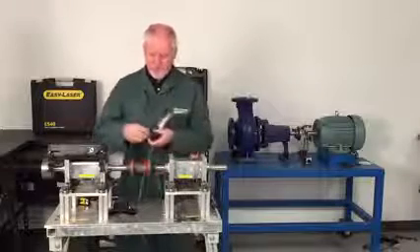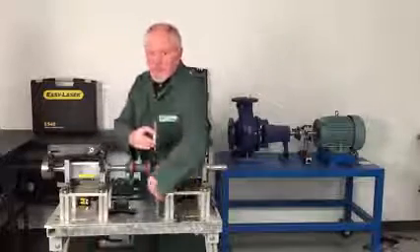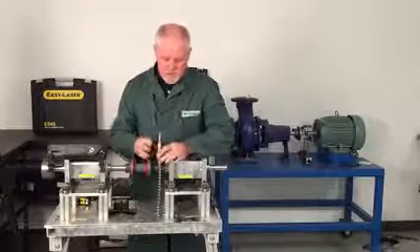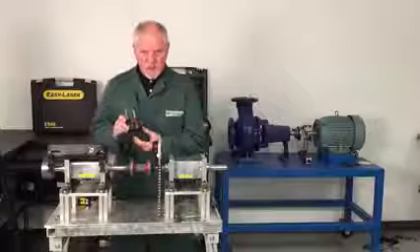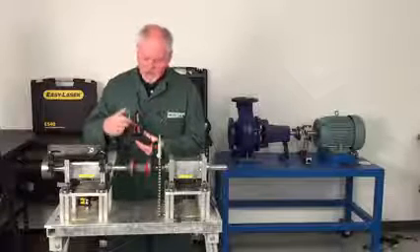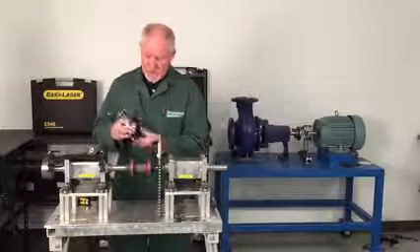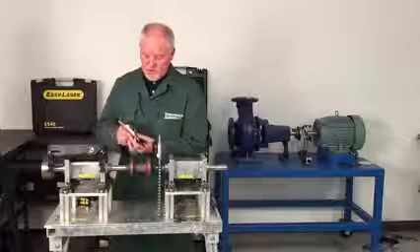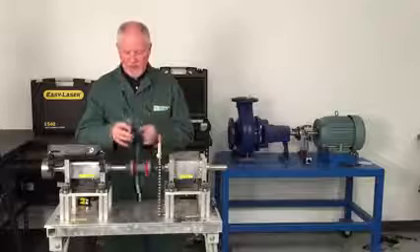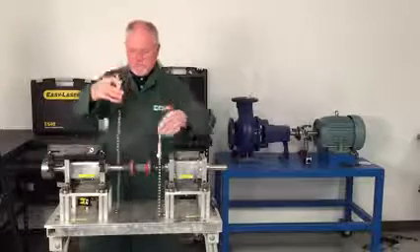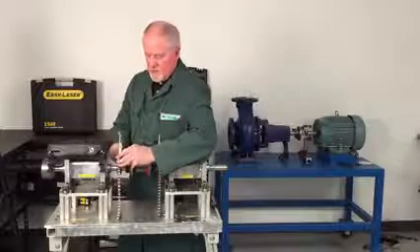And to mount it, all I do is hang the chain from the bracket, pass it under the shaft, and put it on the pin, tighten it up. Now this is exactly the same unit. When it's in the inverse, beam's out on the top, there's the long detector surface. You can see it's got an S on it, and that goes on the stationary side. And to do that, we just simply hang it up the bracket, put it on the pin, and we're on.